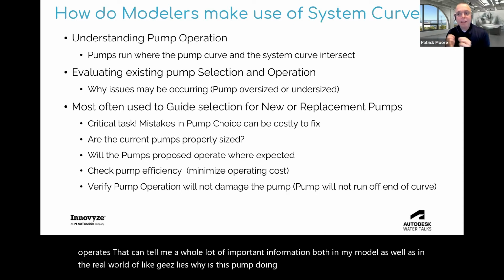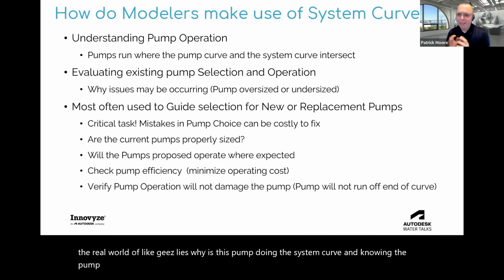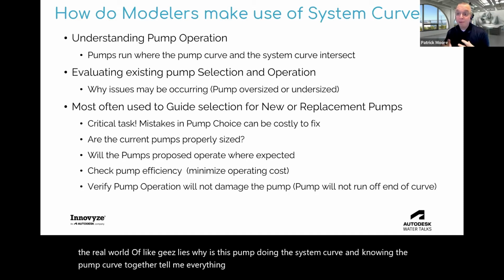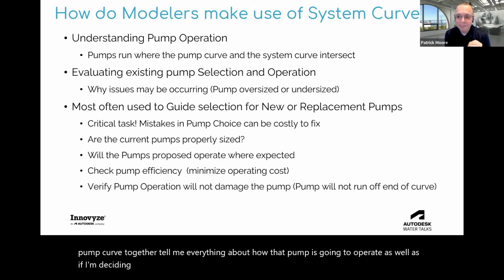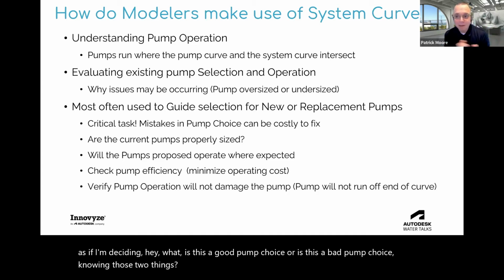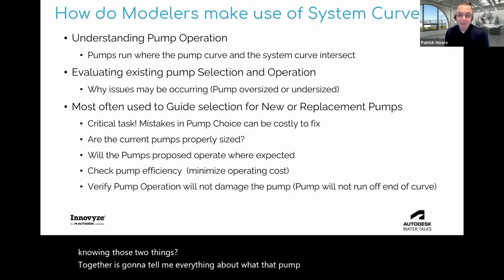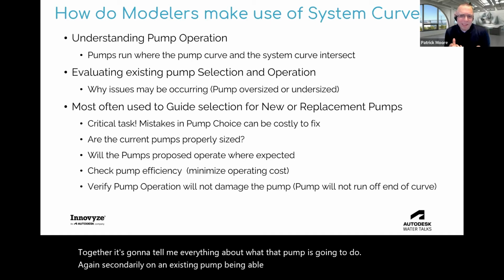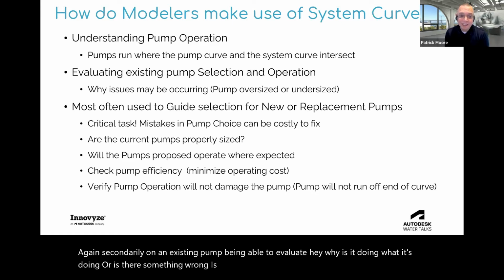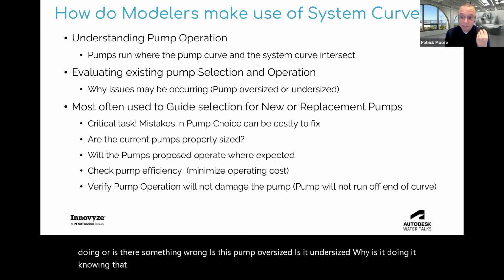The system curve and knowing the pump curve together tell me everything about how that pump is going to operate, as well as if I'm deciding, is this a good pump choice or a bad pump choice? Knowing those two things together is going to tell me everything about what that pump is going to do. Again, secondarily, on an existing pump, being able to evaluate why it is doing what it's doing, or is there something wrong? Is this pump oversized? Is it undersized? Why is it doing it? Having that system curve is often a very useful tool, how people use system curves to do those kinds of things.